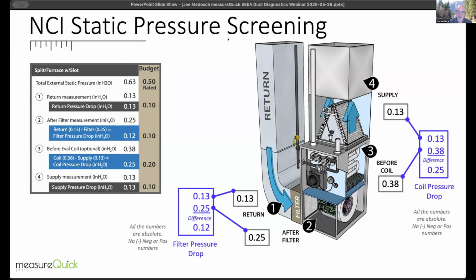So if I want to find out if my return is too small and I have restrictions, or my filter is restricting, or my coil or my supply, whatever those things are that Steve highlighted a few minutes ago on their report, these are the same things you're getting out of MeasureQuick and the NCI static pressure screening. So I could know within a few seconds what my actual issues are. As he highlighted, a lot of times the return is too small or they've got a restricted filter. Those are a lot easier to correct, and a lot of times the restrictions are really near the unit itself. If not, you're trying to figure out how to make this part of your upgrade and diagnostics.